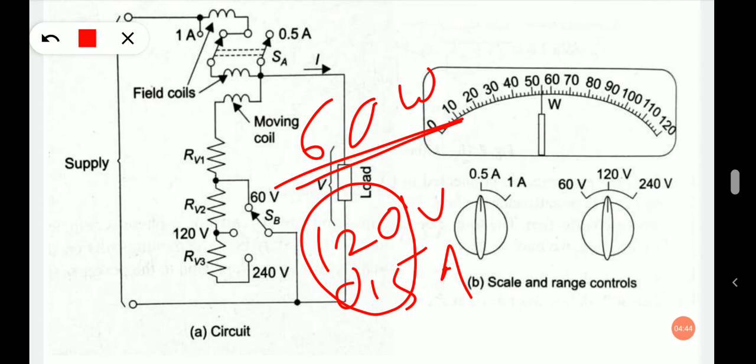This example shows that the meter indicates a reasonable deflection, but the insulation on the moving coil will be destroyed due to overheating, as twice the maximum current flows through the moving coil. Generally, the load for which power measurement is being done has a constant supply voltage which does not change with a change in load current.